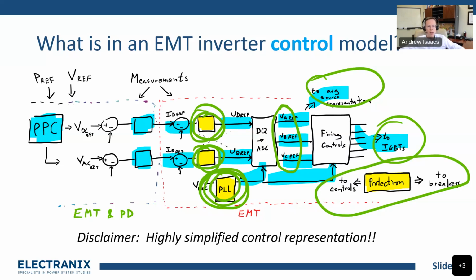You still have your inner current control loops, and for the most part, your protections. What you're missing tends to be just the firing of the IGBTs, which makes that signal noisy. So you miss any potential harmonic issues you might excite in the controls with switching frequencies or specific switching dynamics, which can be an issue, and you can occasionally see ride-through issues with that, but it's not likely.